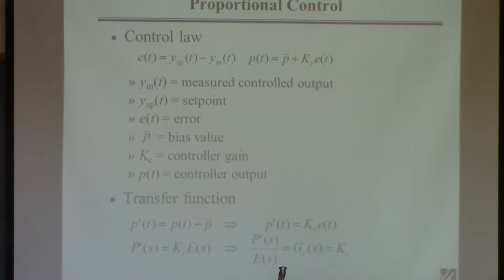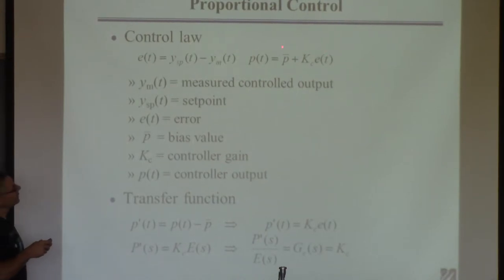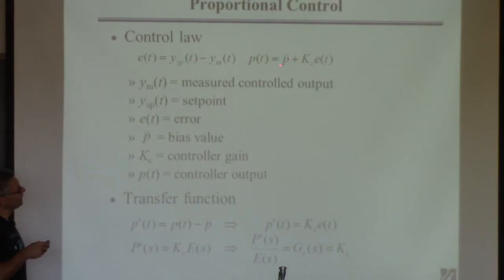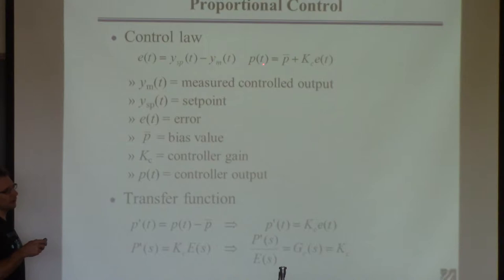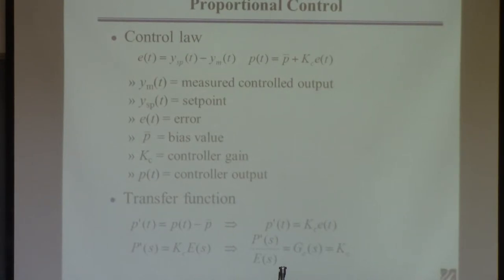How much you act for a given error is determined by the controller gain Kc — an adjustable parameter you have to tune. The bias value compensates for the nominal flow when the error is zero, because zero error doesn't usually correspond to zero flow. Proportional control is the simplest thing we can consider.